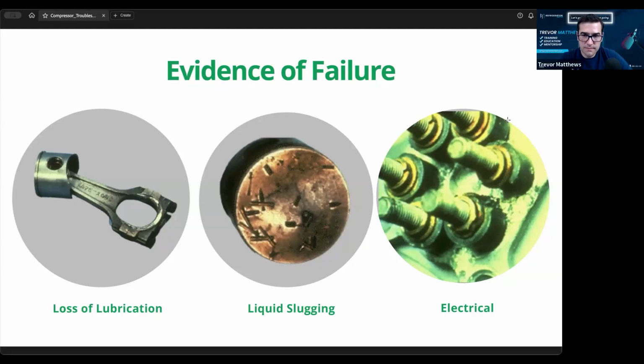Yeah, and we see that in the warranty reports and the teardown reports too, that for the majority of the compressors, there's something wrong in the system. And it is certainly driven by the data that we all see out there in the marketplace. Oh yeah, I've worked with all compressor manufacturers and the numbers are super high. Like we know over 80% is mechanical failures, and that's due to liquid coming back or overheat.